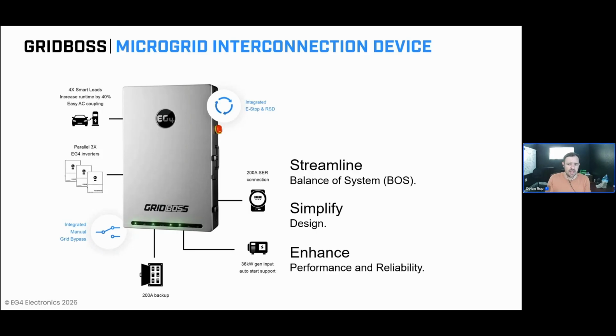Each one of the GridBOSS units encompasses over $5,000 in balance of system components that would be required to be purchased and installed with more traditional energy storage systems. First, it has a 200 amp service entrance rated grid connection if you pair it with an Eaton CSR 200 amp breaker. This removes the need to deploy any service entrance rated equipment prior to the GridBOSS, taking out about $1,000 worth of balance of system requirements. The unit has a generator integration directly embedded in the system, essentially a generator automatic transfer switch. And it features both auto start and generator exercise functionality included, giving you the ability to attach up to a 36 kilowatt generator directly into the GridBOSS and have all the same functionalities that you would see with a traditional ATS, and having that generator now be an integral part of the home's energy system, all managed intelligently by the energy storage system.